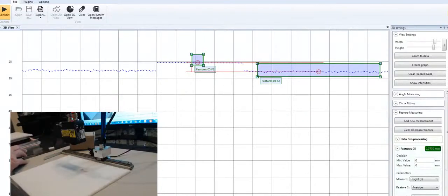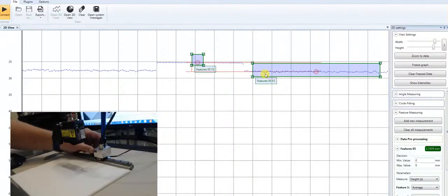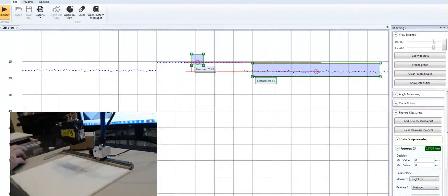And here you can see that we're getting a little bit of difference in measurement, right? So it's showing 2.7. So it's creating a 7/10 offset, showing that from this surface to this surface is further away than it should be. So it is penetrating quite a bit into that surface. So let's go ahead and move the scan a little bit and see if we are seeing that same offset because of that.